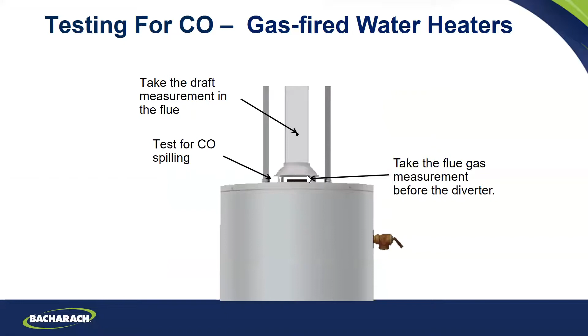The problem, at the end of the story, was he had a lot of kids and a swimming pool in the back, and he was mixing his swimming pool chemicals down in his basement by the water heater. Those chemicals have chlorine in them, and anytime you take chlorine and heat it up, you make hydrochloric acid. That twisted piece of metal that slows the gases down is hung on right up here with little pieces of metal, like little ears, little hooks. The hydrochloric acid ate those little hooks, and the metal just slid right down and sat on top of the burner. That caused flame impingement, and it made over 8,000 parts per million CO.